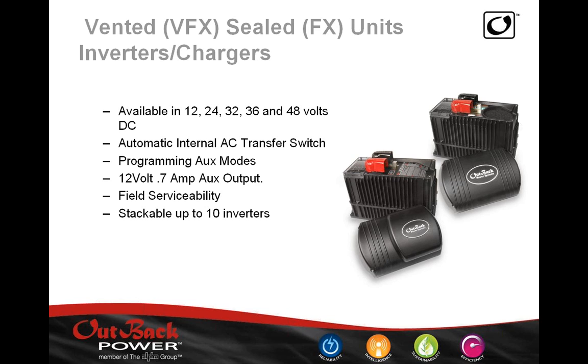The input voltages go from 12 volts to 48 volts. They both have the same function in terms of working in a backup application. In addition to the 120 volt output, they also have a 12 volt 700 milliamp output that can be programmed to implement logic, like starting an automatic generator, a fan, or a light, really any type of logic that you want based on voltages.